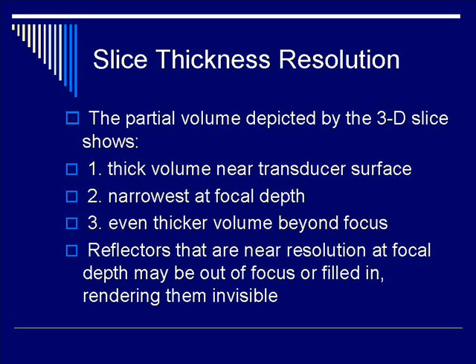The partial volume depicted in the previous slide showed that slice-thickness has a thick volume near the transducer surface. It is narrowest at the focal depth. As it fans out beyond the focal distance, it has an even thicker volume compared to at the surface. Therefore, if you're trying to resolve reflectors that are near the resolution limit of the transducer element at the focal depth, you'll become out of focus if you're going away from the focal zone.